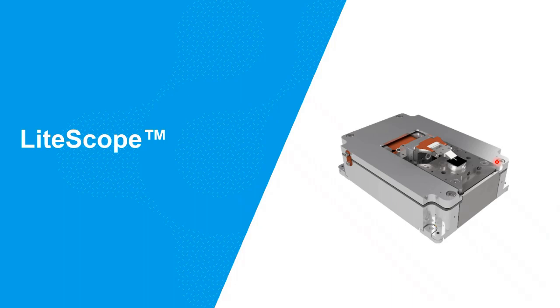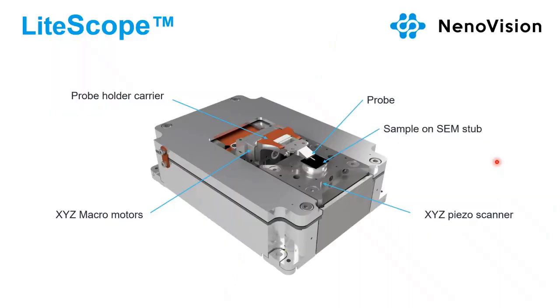And so let's move to the LiteScope itself. The LiteScope head is composed of the scanner, on which is the sample in a usual SEM stub. There is a probe inside of a probe holder carrier, and there are macromotors. So you can use the stage for moving under the objective, and then scanner and probe can be moved separately.